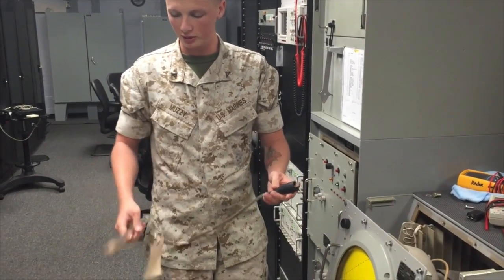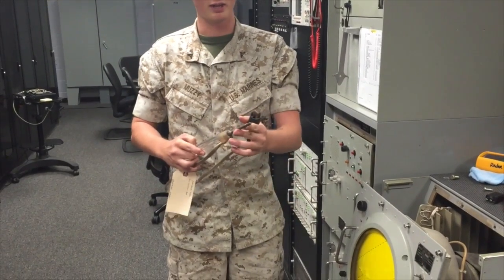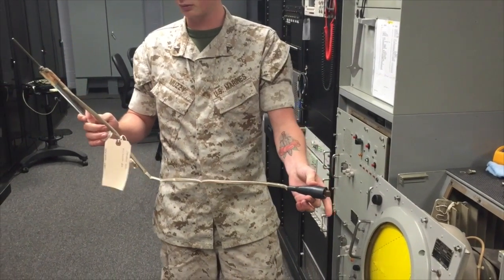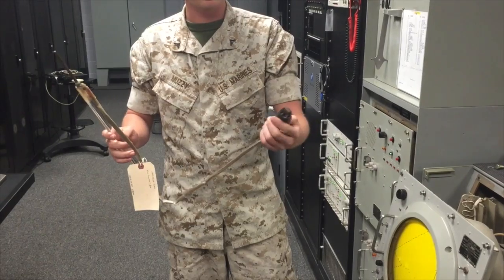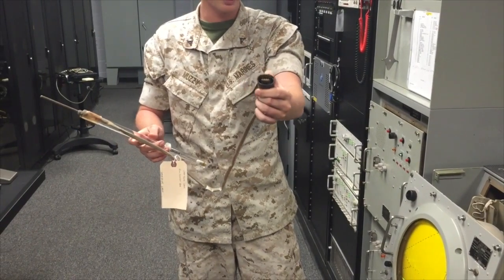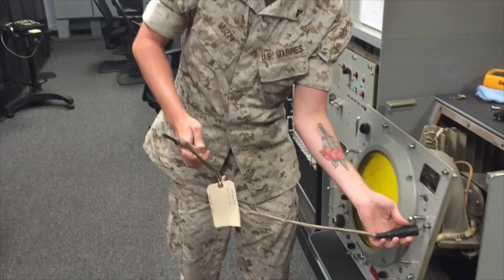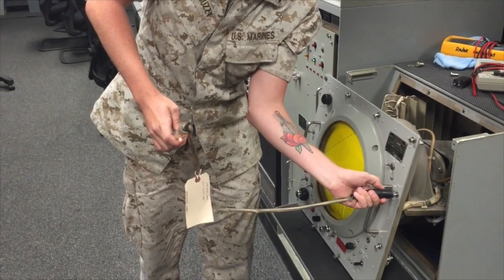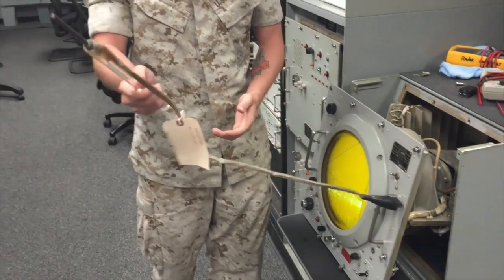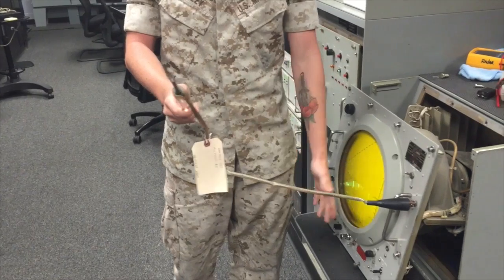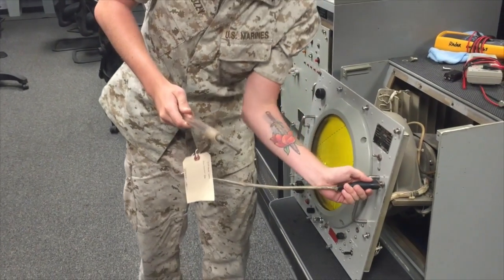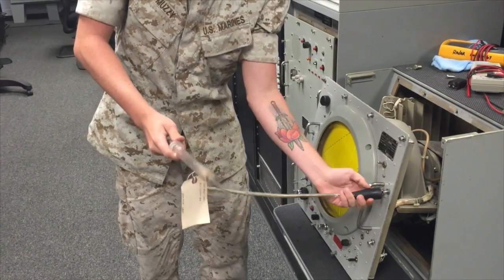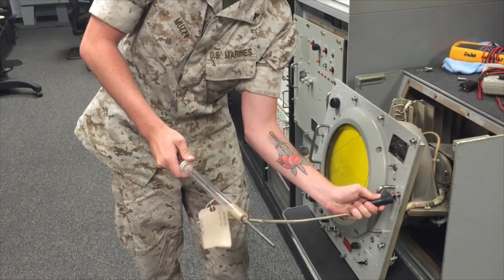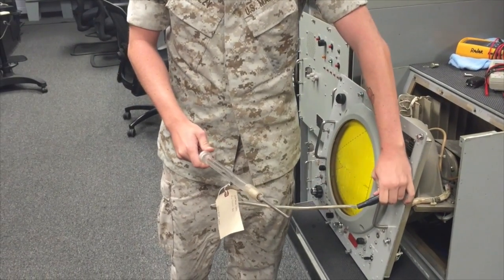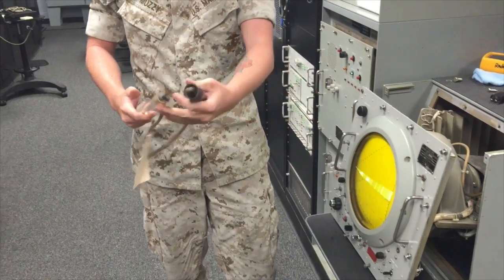The shorting probes consist of an insulated handle, the metallic tip, and the grounding cable. At the end of the grounding cable, you have a clip that you can attach to any of the screws on the front of the indicator to ensure the electricity passing from the probe goes straight to ground and disperses. The handle is separate from the probe because it's made of a high resistance, non-conductive plastic, as is the cord.